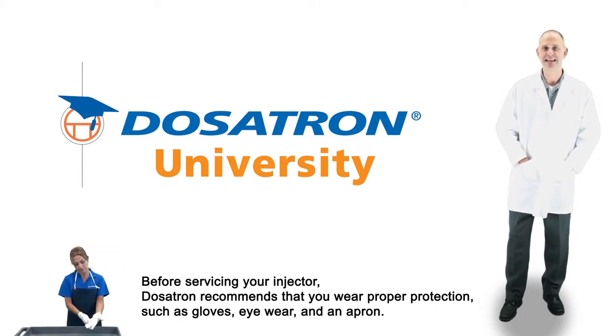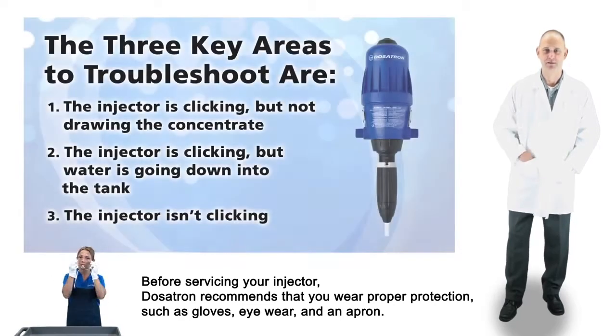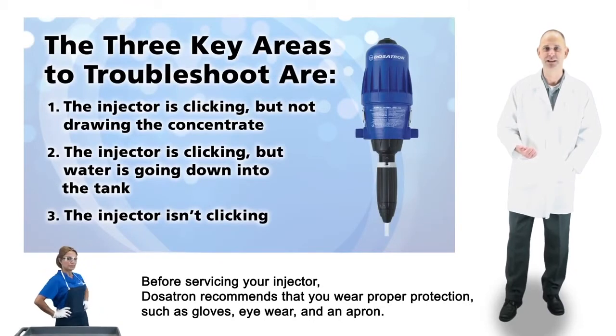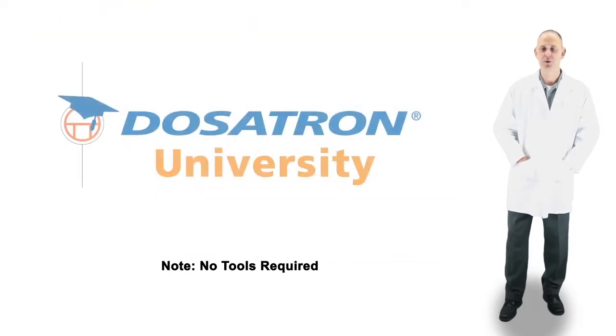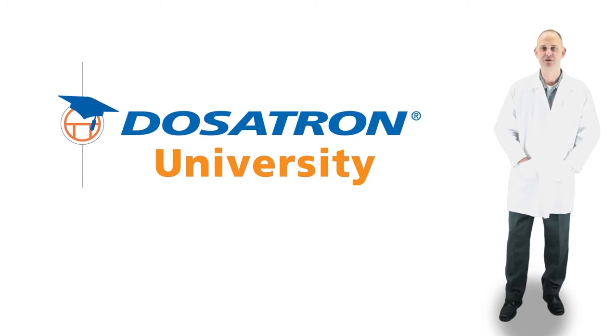The three key areas to troubleshooting are: number one, the injector is clicking but not drawing the concentrate; number two, the injector is clicking but water is going down into the tank; or number three, the injector isn't clicking. The first two are the most common. If the injector is clicking but not drawing or it is pushing liquid down into the tank, the issue is in the stem area.